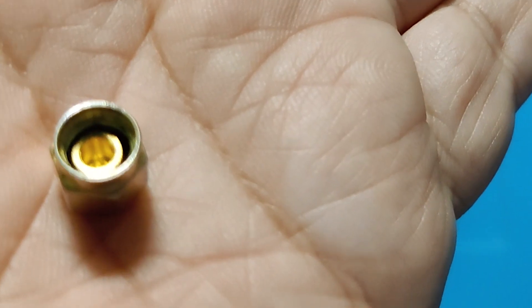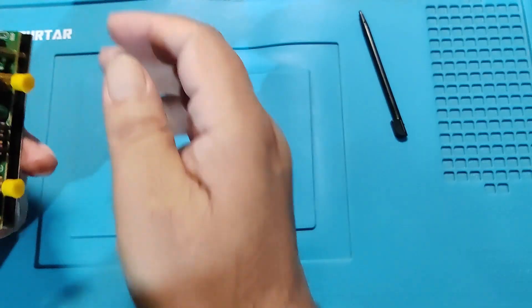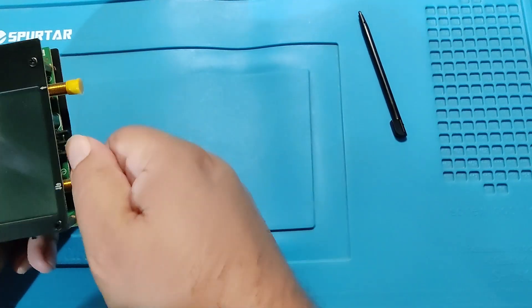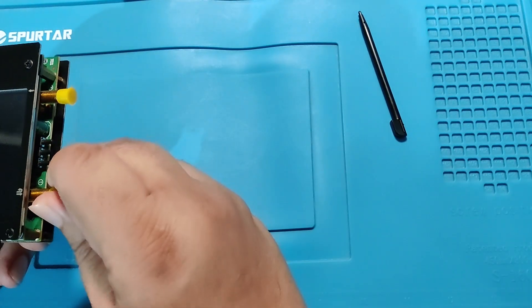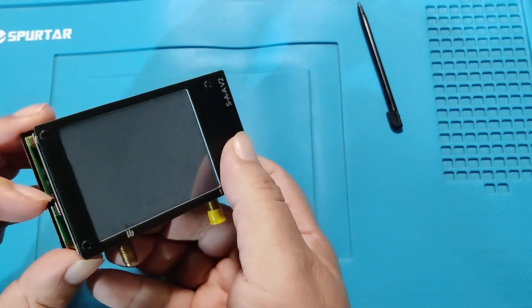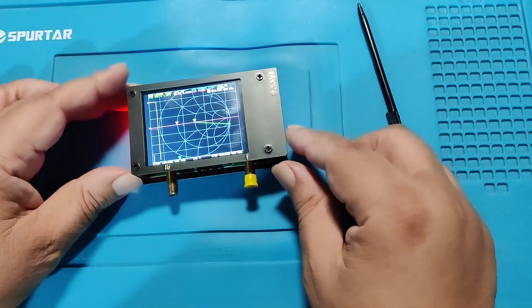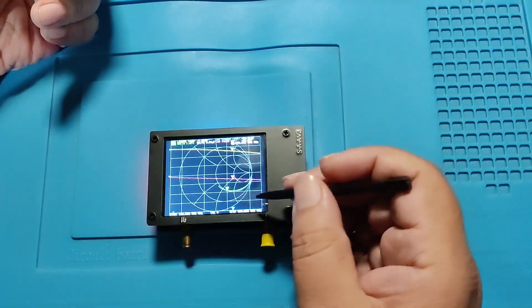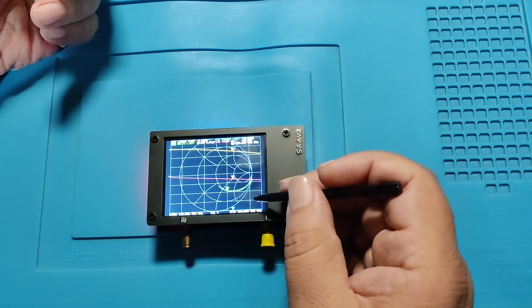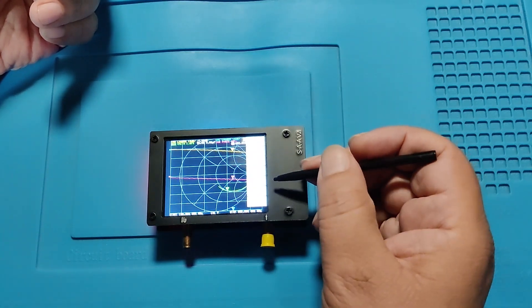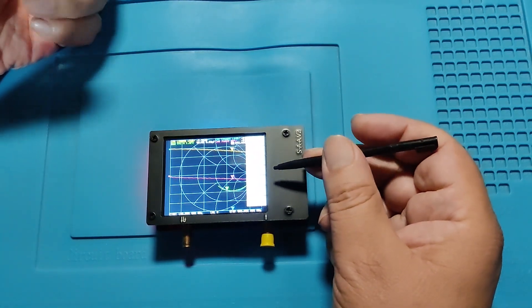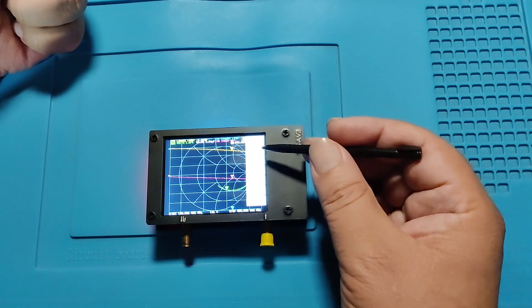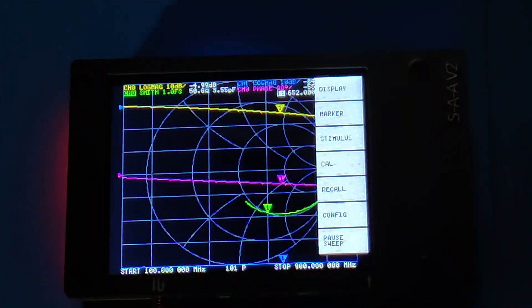I will remove the yellow dust cover from the S11 line and switch on the device. To calibrate, our first step is to open the menu by clicking on the right side, and on some VNAs, on the left side of the screen.